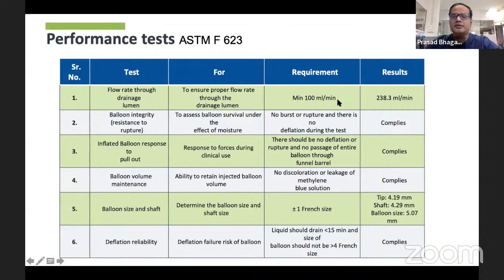The minimum flow rate requirement is 100 ml per minute, and the result we have got is 238.3 ml per minute, which means the urine flows unobstructed through our catheter and is released at the back, which is the ideal situation. Second is balloon integrity and resistance to rupture. As you all know, the balloon is inflated and is continuously in contact with the urine, that is the moisture, and whether this balloon can withstand that moisture, and for how many days, is assessed in this balloon integrity test.